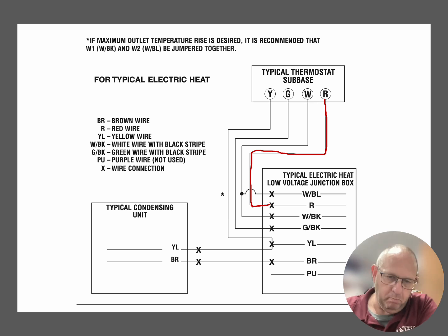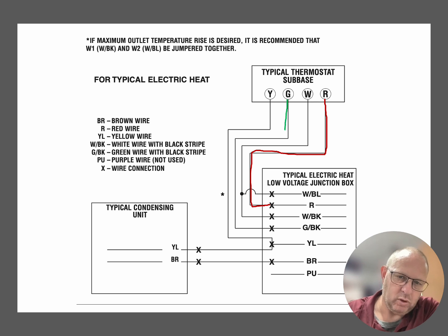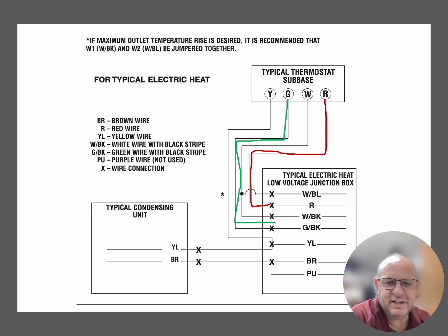indoor fan. Now, most air conditioning systems, the G wire will actually be energized when the cooling is going to be energized. Then the board will decide whether to turn on the G, or if it gets a Y signal, then it will turn on the high speed or the cooling speed, whatever one it is. The yellow, and I want you guys to notice this because a lot of people make this mistake when they're installing these systems. That yellow wire ends up inside on the indoor unit. And after it ends up on the inside, we'll take a wire nut and we'll run that unit to the outdoor unit sitting right there. So that's typically how it goes.